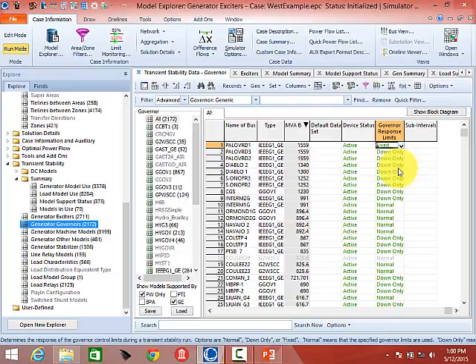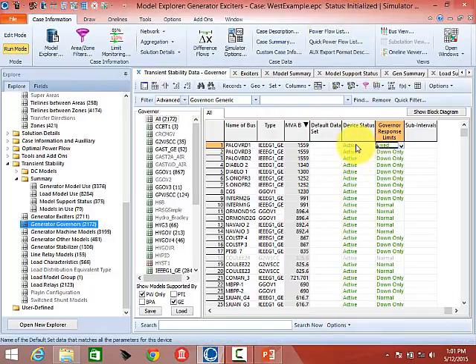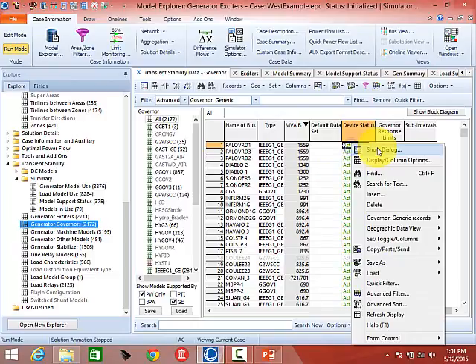We're going to move on to small system studies with transient stability plots. To net a generator, you can set the machine model to inactive and PowerWorld will net it. If I want to quickly disable a generator, I go to its machine model and set it as not active. If the machine model is not active, none of the other models are active either — it doesn't make sense to have an exciter without a machine.